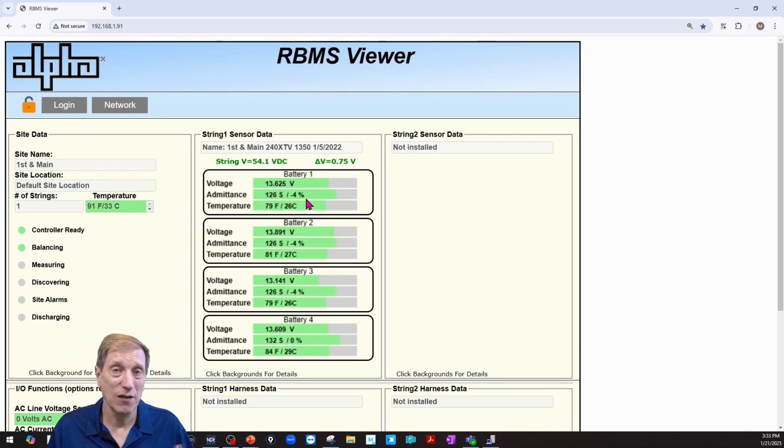But if you've got one at -40 and all the rest are like -4%, 2%, 5%, even 10%, and that battery started at about the same point, that battery's failing prematurely, okay? So that's what you're looking for. Are they grouped together and all about the same value? Or do you have an outlier that's failing way early and coming in with those higher numbers? That's how you know whether the string is just aging or you've got a failed battery.